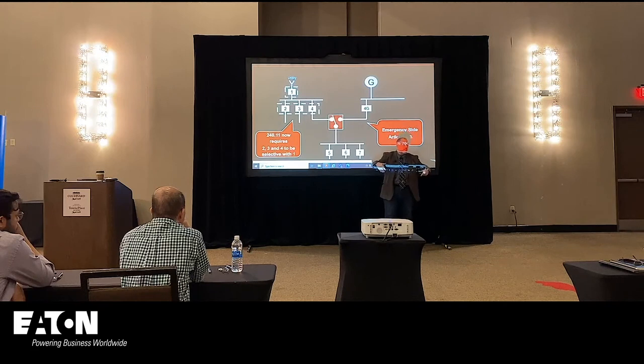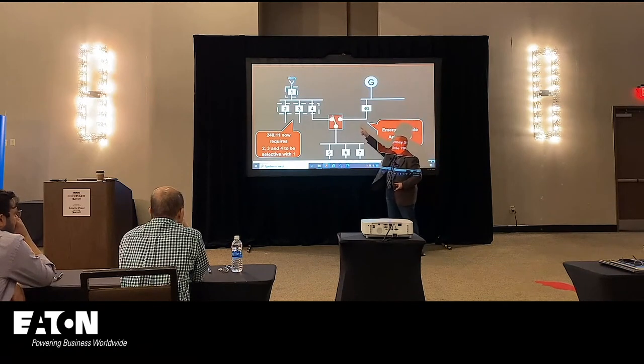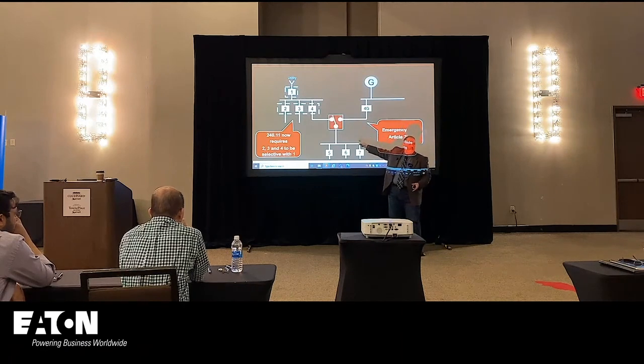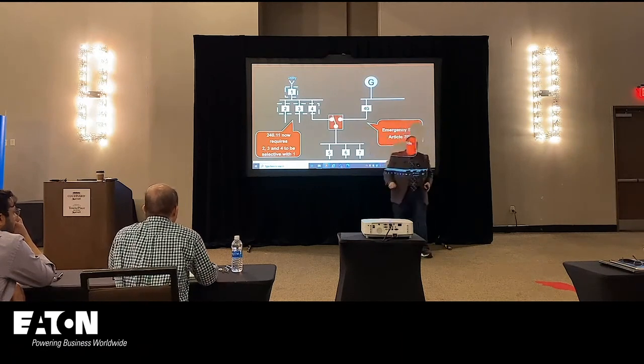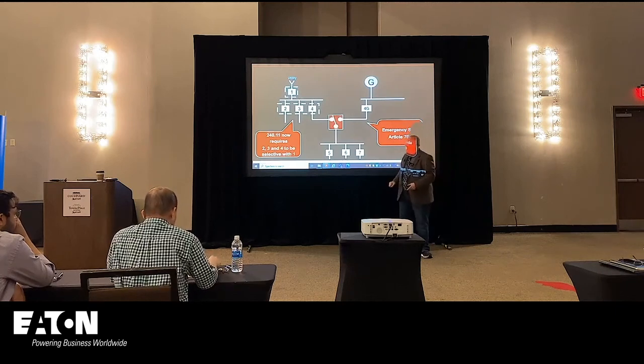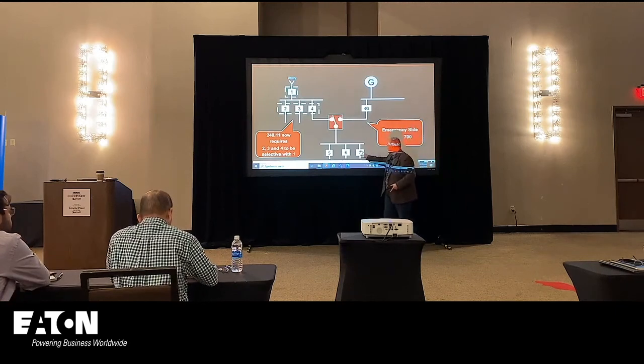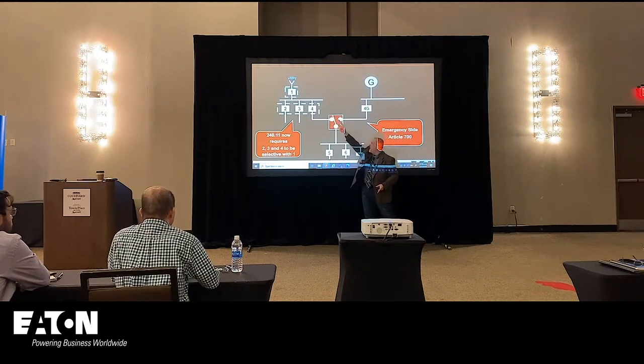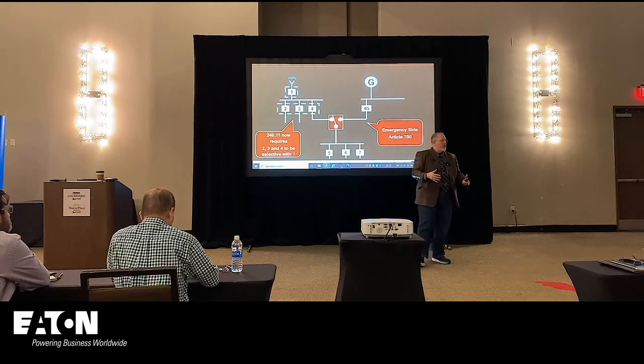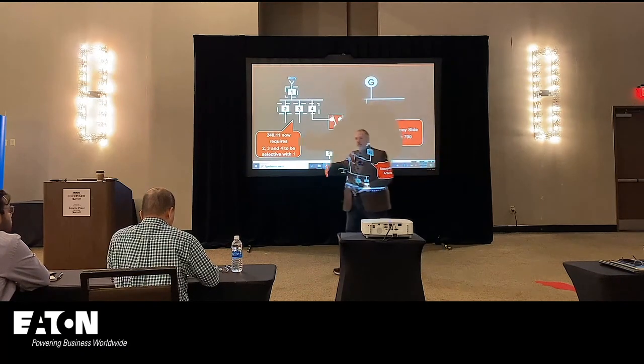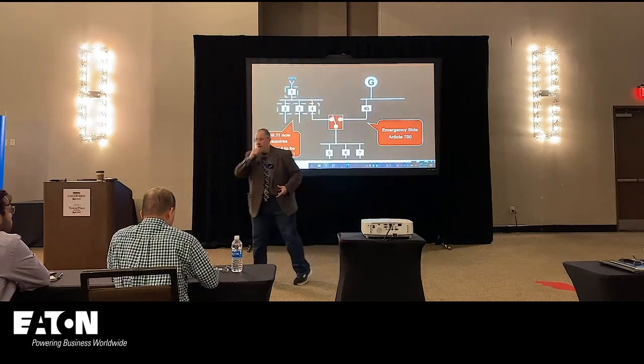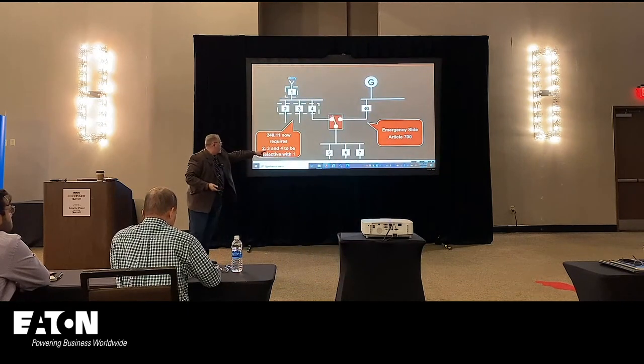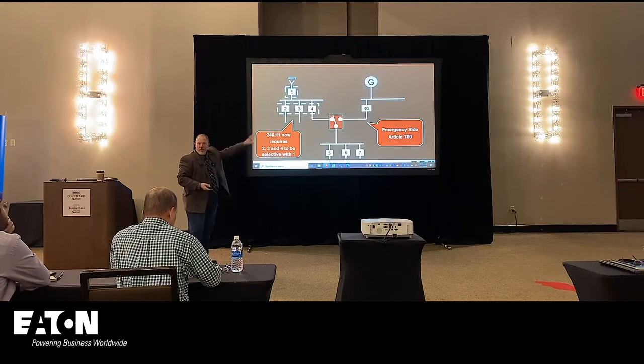The big debate has been, panel 13 always gets public inputs and says, well, what about devices 1 and 4 that goes to that transfer switch? Do I have to selectively coordinate 1 and 4? So panel 13 said, no, look, you have to selectively coordinate 7 with 4G and 7 with 4 and 7 with 1, but 4 and 1 are outside of the purview of Article 700 because they're on the normal side. Article 700 can't tell you what to do on the normal side. They can tell you what to do between 7, 4, and 7 and 1, but the onus is on 7, not those other 2.